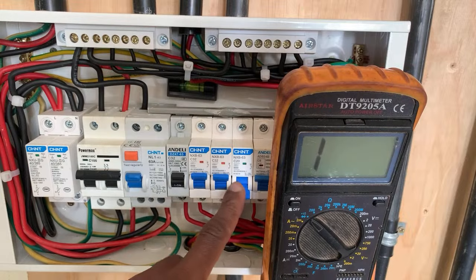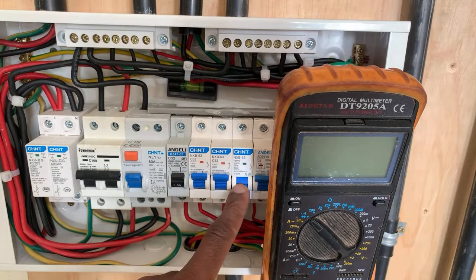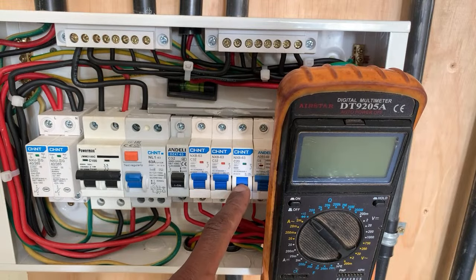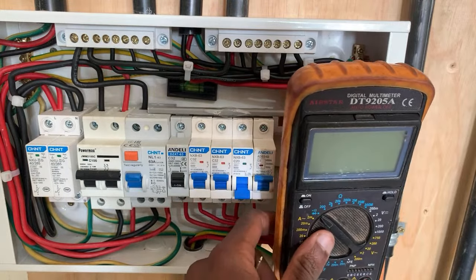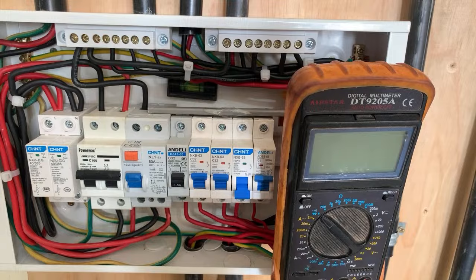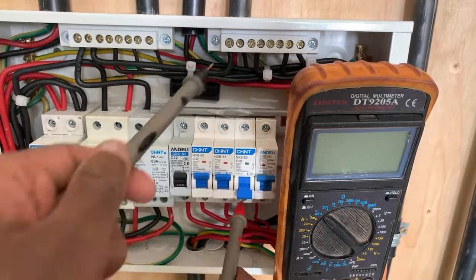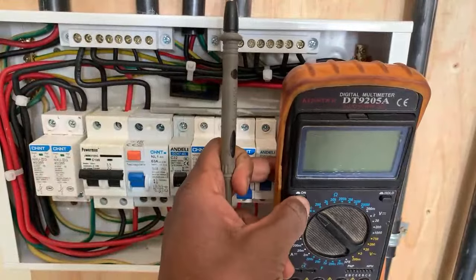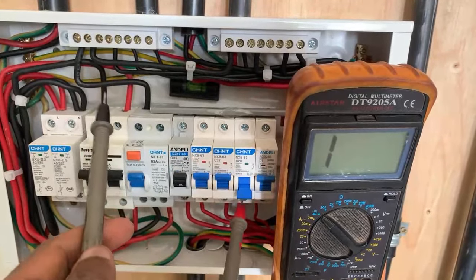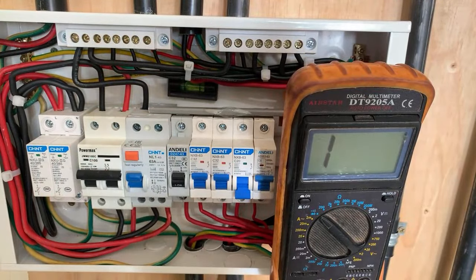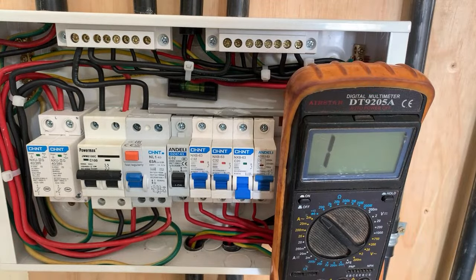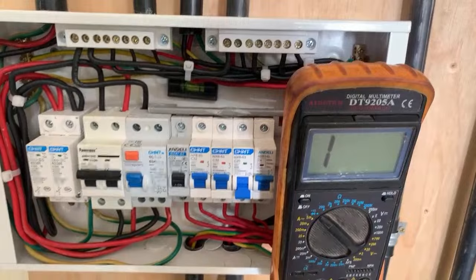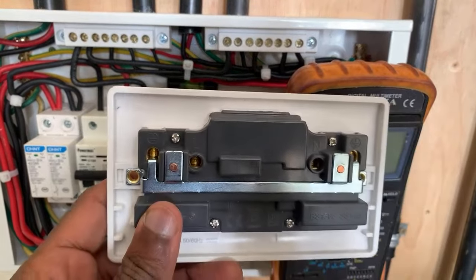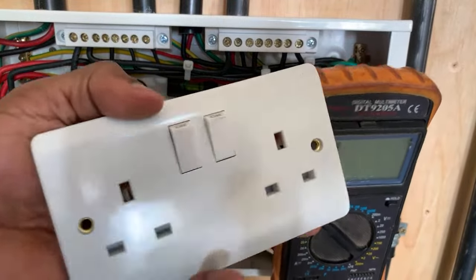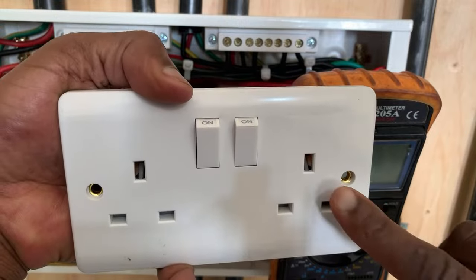So this is our circuit breaker here, the MCB. It is already down, and we have that issue of the short circuit. Now, what if you have already resolved the issue of the pump, and you came and did this troubleshooting here, sorry, my meter is already off, it is automatic. You went to the socket and indeed discovered that the socket had also short-circuited. Let me demonstrate. Assuming this is the socket that is connected to the pump, the pump was drawing power from this socket.